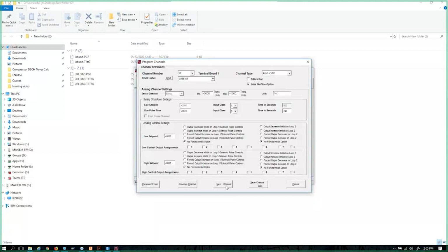Lubrication channels. So this was a fun feature that we introduced in 2014 when we released the enhanced or version 2X DE-3000 as well. Channel 27 and 28 are the only two channels in the 3000 that can do this lube no flow option. And what the option is, rather than using a ProFlow device or a simple Chemray no flow device, or the more common term, I think, is the DNFT, Digital No Flow Timer, we can use a simple proximity switch, or we can use the proximity switch feature only from those modern day DNFTs. So rather than them triggering the fault for us, we now can set up a time sequence to where we monitor the time in seconds between a full cycle of the lube system through that proximity switch. So it's a little bit of a hybrid channel, if you will.